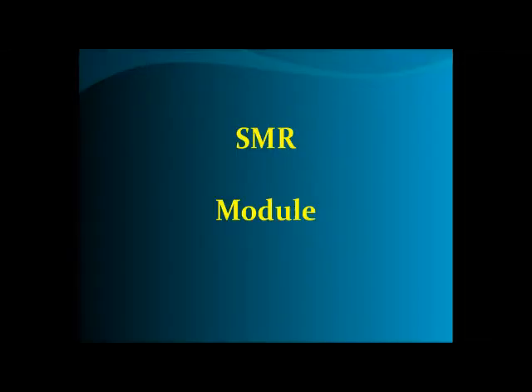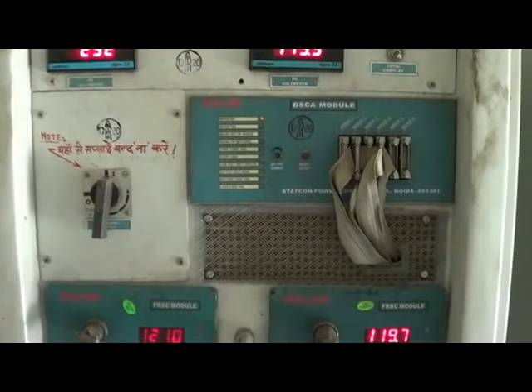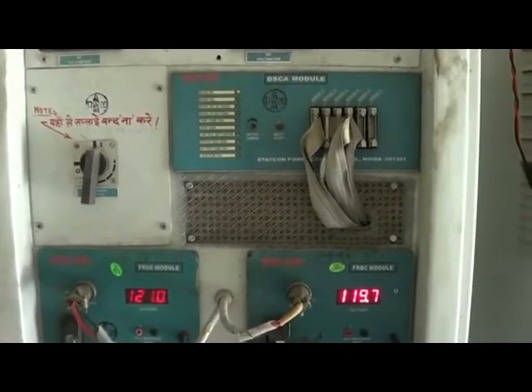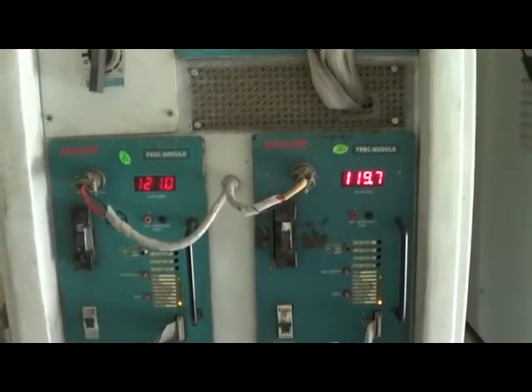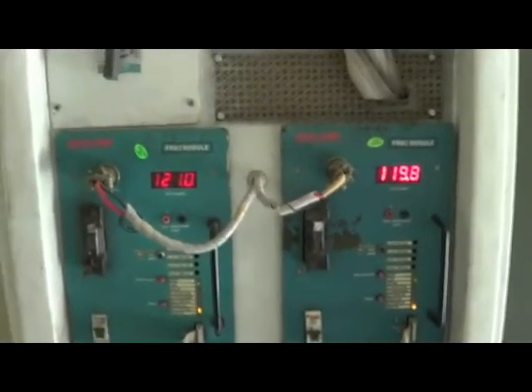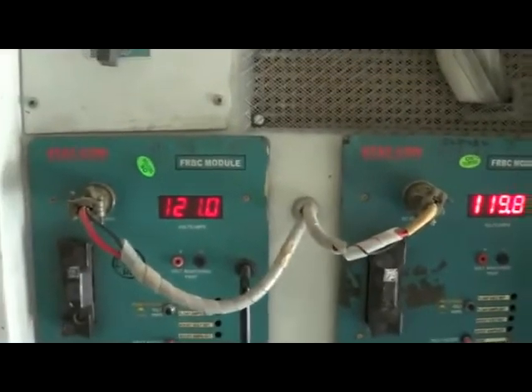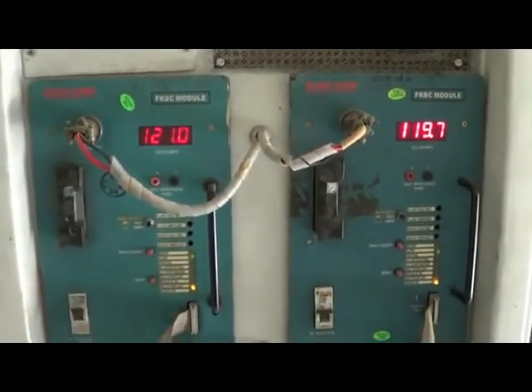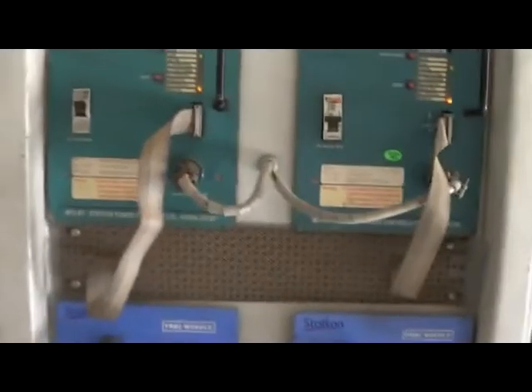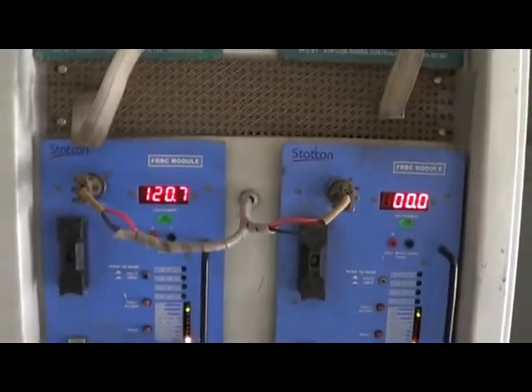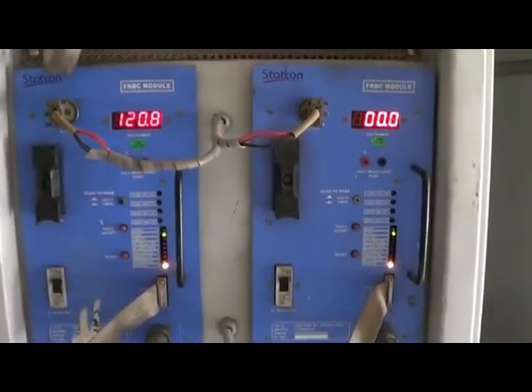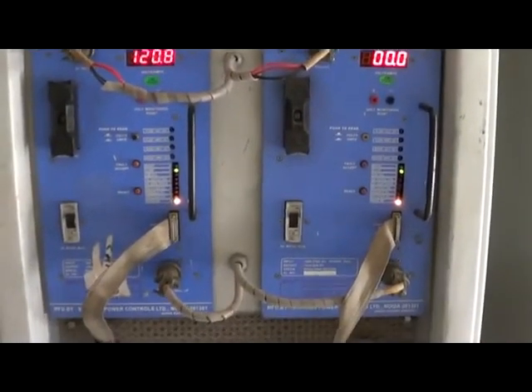The SMR panel consists of the FRBC (Float Rectifier Boost Charger) module. The FRBC modules are connected in an N+1 configuration, with each module rated at 110 volt, 20 ampere.